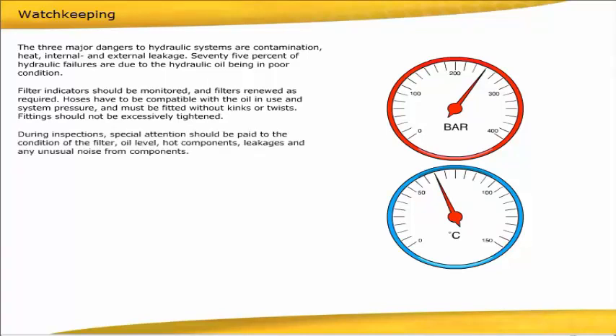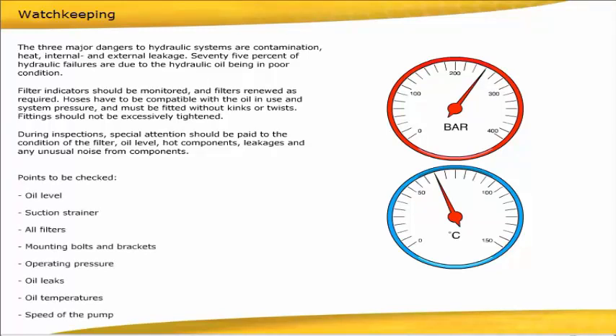During inspections, special attention should be paid to the condition of the filter, oil level, hot components, leakages, and any unusual noise from components. Points to be checked: oil level, suction strainer, all filters, mounting bolts and brackets, operating pressure, oil leaks, oil temperatures, and speed of the pump.